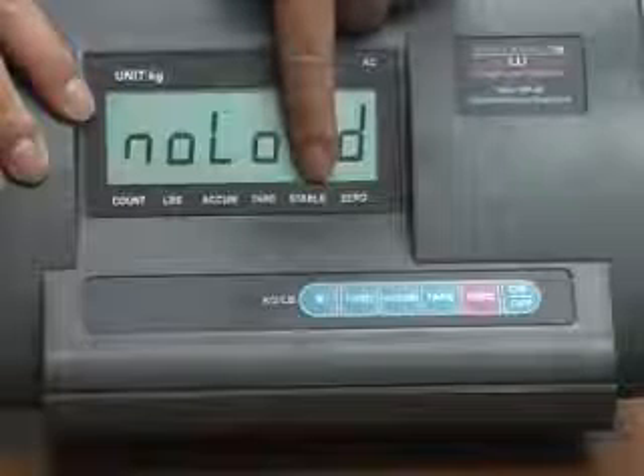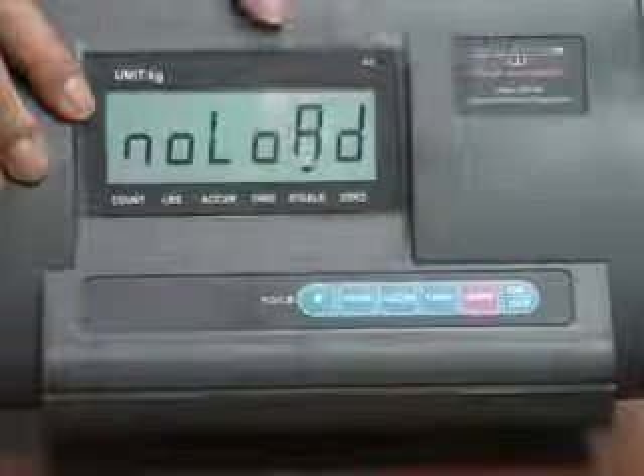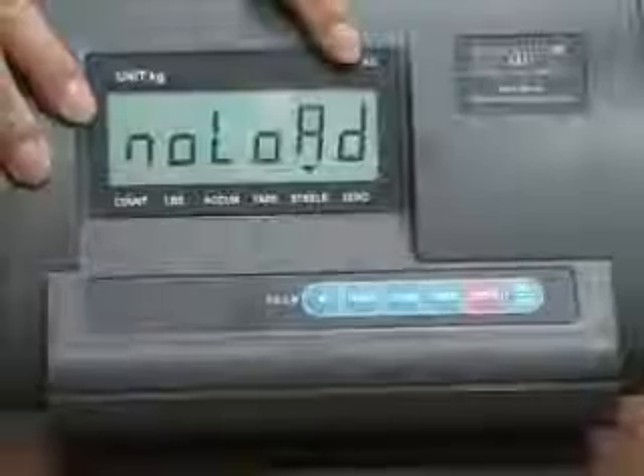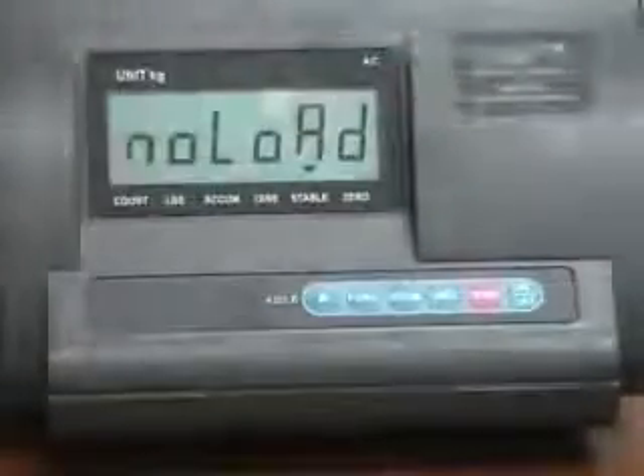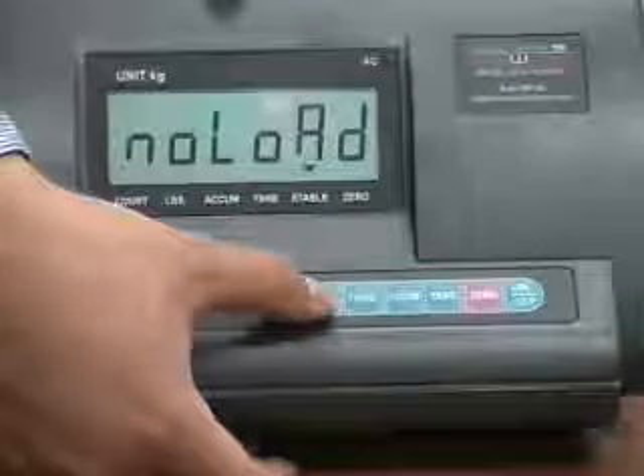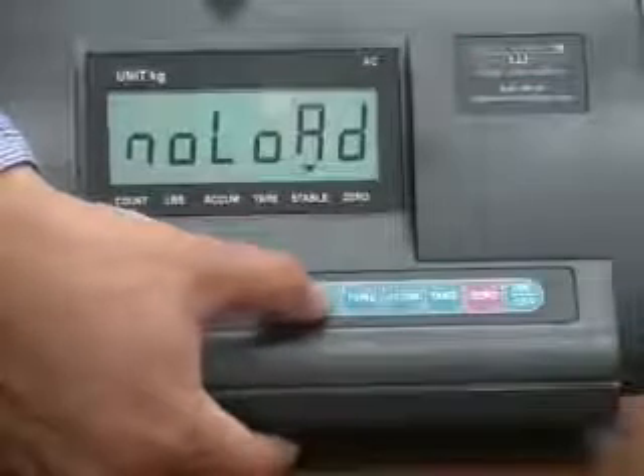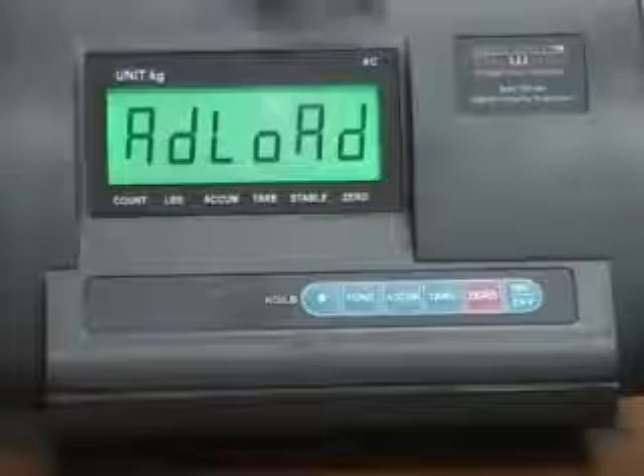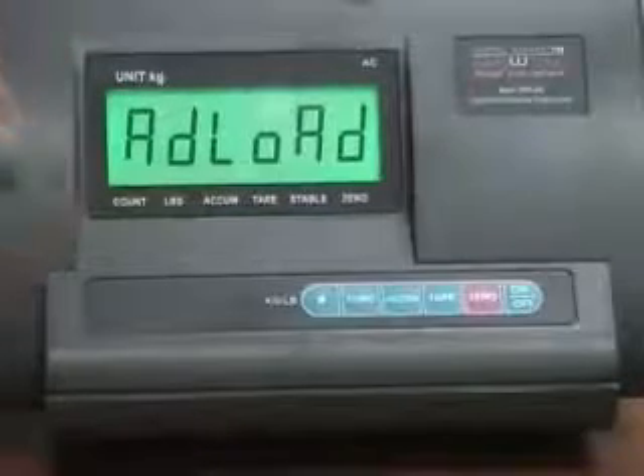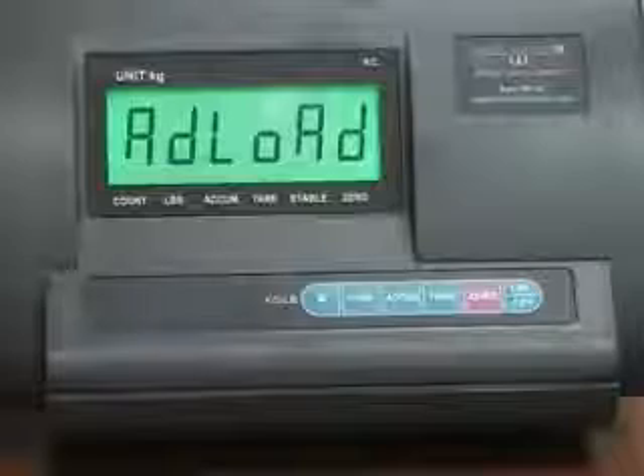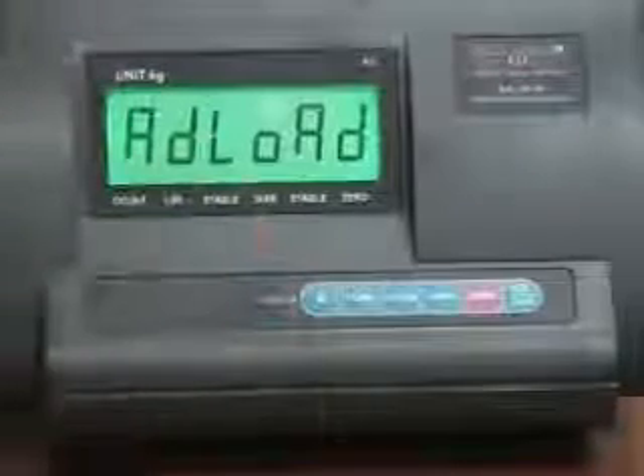Under no load, you need to see a little indication right above stable. That means you got the signal from the base. When you see that, make sure there's nothing on the platform. Wait about 3 seconds, then you can press the pound key to confirm. Now it gives you add load. Add load means you need to input the value of the calibration weight. In this case, we have 25 kg.